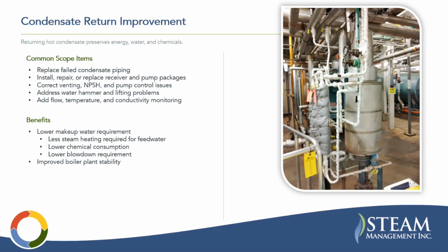The benefits of improving your condensate return: you're going to get a lower makeup water requirement, and that is from less steam heating required for the feed water. The benefit of requiring less makeup water is that you've conserved some heat, so you have less steam heating required for your feed water because you're returning more hot condensate instead of cold makeup water. You're going to have lower chemical consumption because it's now less makeup water to be treated, and you're going to have lower blowdown requirement, which we'll talk about in a bit.